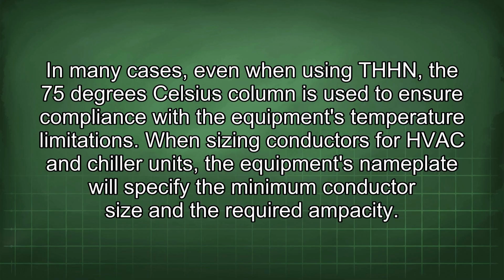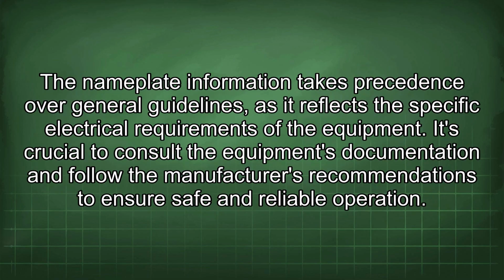When sizing conductors for HVAC and chiller units, the equipment's nameplate will specify the minimum conductor size and the required ampacity. The nameplate information takes precedence over general guidelines as it reflects the specific electrical requirements of the equipment. It's crucial to consult the equipment's documentation and follow the manufacturer's recommendations to ensure safe and reliable operation.